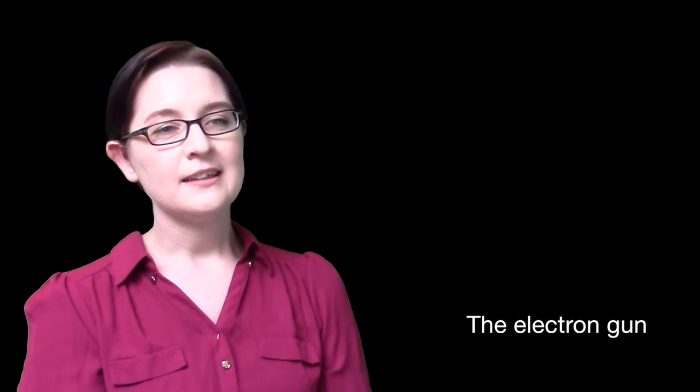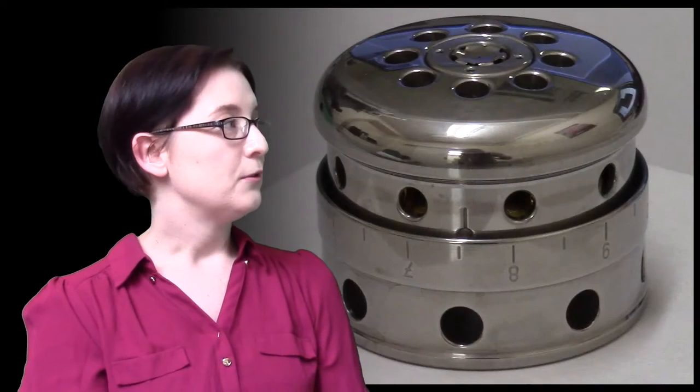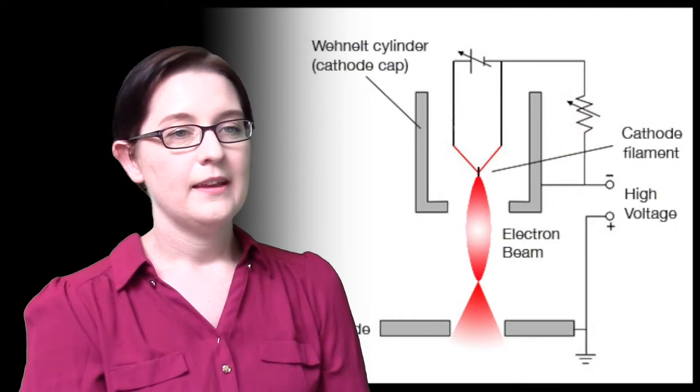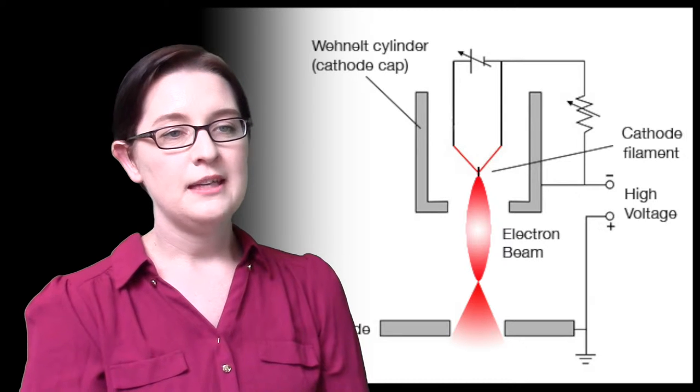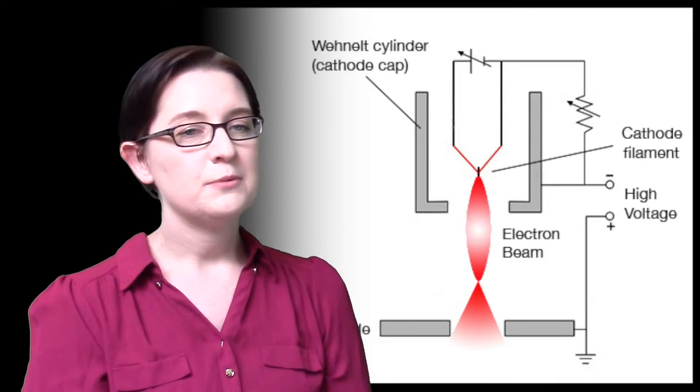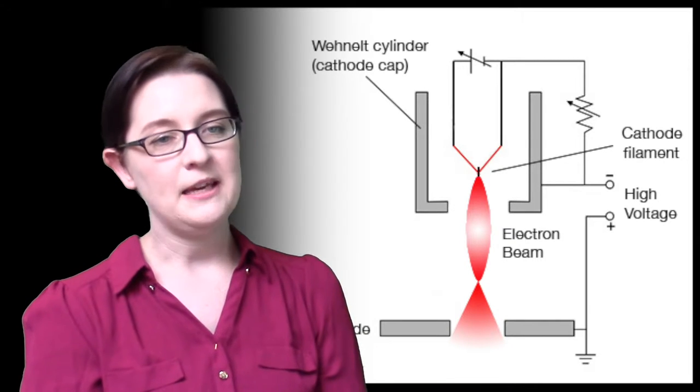The electron gun consists of an electron source—the filament, which also acts as the cathode—shield, and anode. A current is run through the filament to heat it, resulting in the emission of electrons from the tip. The high voltage difference between the shield and the anode causes the electrons to accelerate and form a beam.